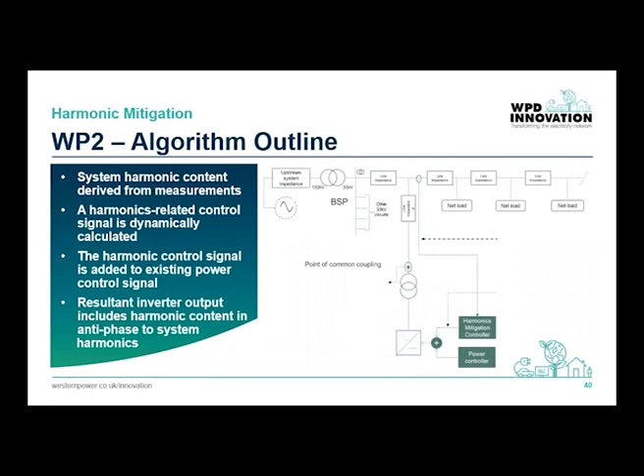This slide provides a high-level overview of how that works. In this instance, the algorithm samples current from the 33 kV feeder downstream of the inverter, effectively measuring cumulative downstream load on the feeder. From this measurement, the harmonic content is established. This harmonic content is compared to the harmonic set points, and a harmonic controller generates control signals based on the difference between the actual harmonics and the desired set point values.